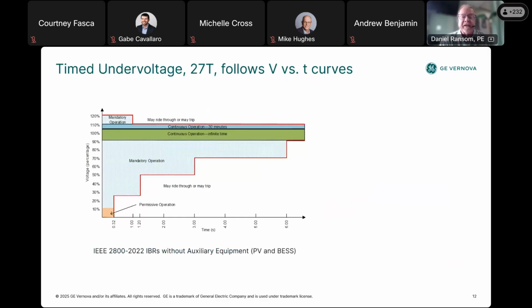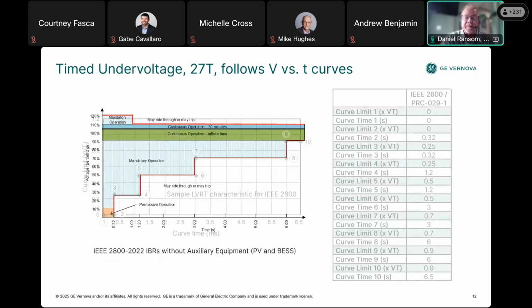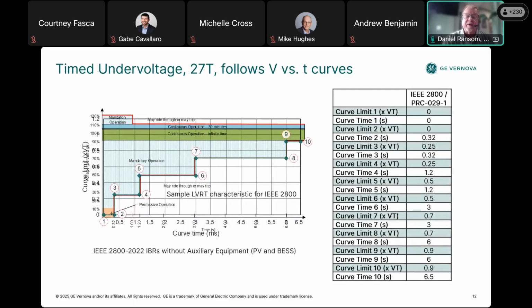So how can a protective relay help the IBR plant get this right? Well, here's how. We've got a timed undervoltage 27T element that follows the V versus T curves. If you were to do this in a conventional relay, you would need lots of undervoltage elements. So we've made one that'll track on a graphical basis. It's a timed and count qualified phase undervoltage 27T element, and it keeps the IBR operating to prevent grid collapse. It's time dependent. It has 10 configurable points.